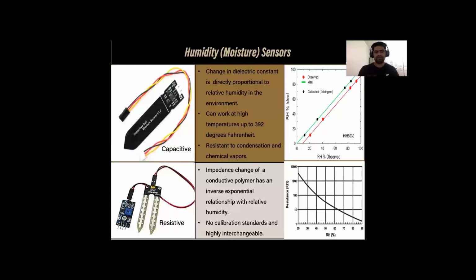These are the calibration curves of different humidity sensors, which highlight the ideal calibrations and the relationship between the input variable and the output - the measurable parameter we are interested in measuring. Capacitive humidity sensors can work at higher ranges of temperature, and they are also very stable, resistant to condensation and chemical vapors.